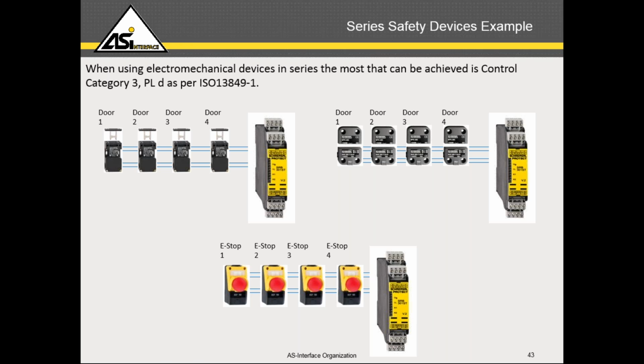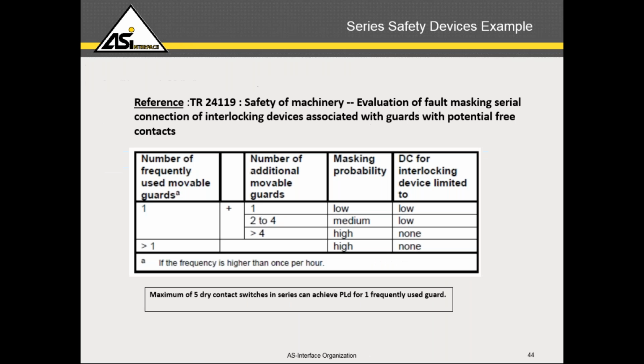The highest level of safety that you can have is Category 3, Performance Level D. But there is more to this than you think, as this issue has been recognized as a critical issue when door switches are series connected, especially when they're frequently used. When they're frequently used, you may think that you're getting Category 3 Performance Level D, but you may not. This guidance actually comes from the ISO 14119 standard, which discusses interlocking devices and the design aspects of interlocking devices.